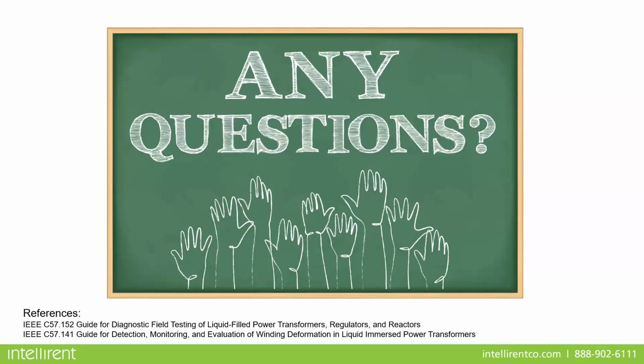And it's interesting, I've been involved in monitoring for 20 years or more now. Yes, some transformers are equipped with bushing monitoring, and yes, some bushings do fail. It's been my experience that when you go out and ask the embarrassing questions to customers, like, "I download the data from the monitor, and obviously there was an alarm, here's the time and date. What did you do?" Well, we didn't know, because nobody connected the relay alarm contacts on the monitor into SCADA or into a data acquisition system. And some people, the transformer person, say, "That's not my job. That's the SCADA guy's job." Unfortunately, that has happened. And Drew, you've probably seen that before yourself. Yeah, absolutely.